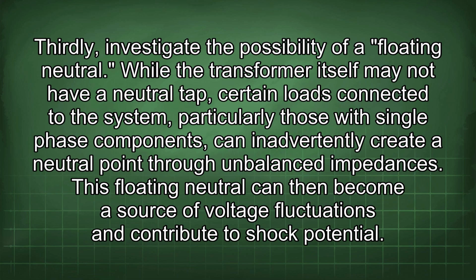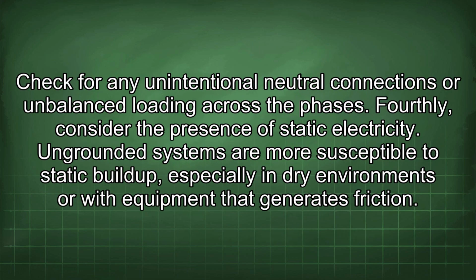Thirdly, investigate the possibility of a floating neutral. While the transformer itself may not have a neutral tap, certain loads connected to the system, particularly those with single-phase components, can inadvertently create a neutral point through unbalanced impedances. This floating neutral can then become a source of voltage fluctuations and contribute to shock potential. Check for any unintentional neutral connections or unbalanced loading across the phases.